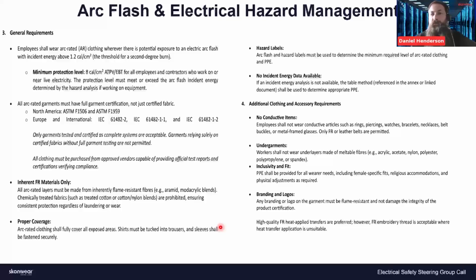Where the levels come from, so hazard labels, where you haven't got any incident energy data, so when we use the table method, and then just additional processes around what you'd wear underneath, so you haven't got any additional fuel, what you'd wear with it. And then one big point again is any branding or logos have got to be flame resistant, not damage the integrity of the product.